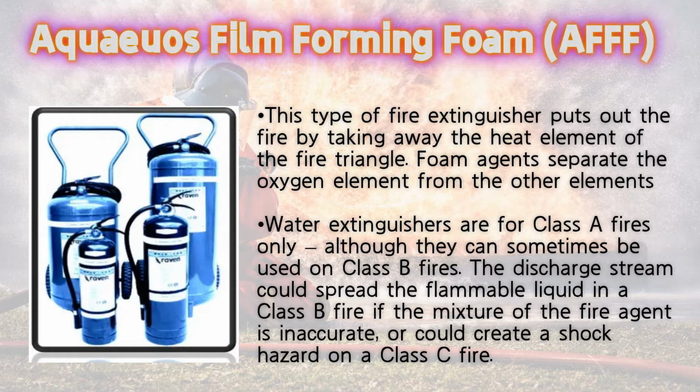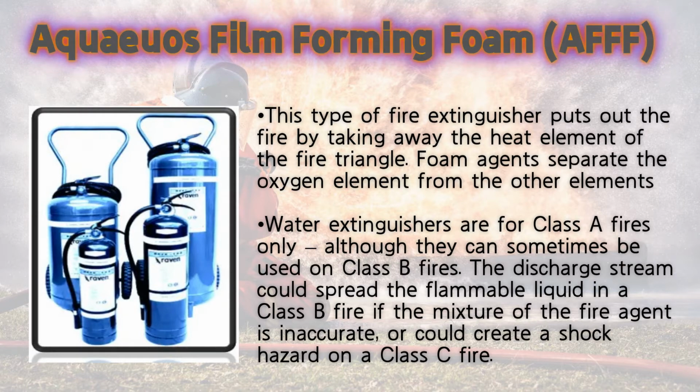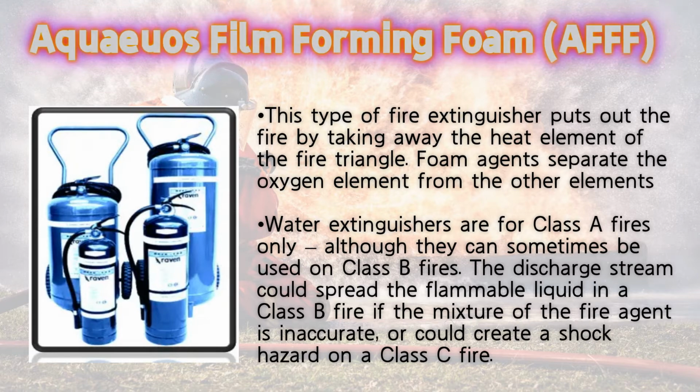Water extinguishers are for Class A fires only, although they can sometimes be used on Class B fires. The discharge stream could spread the flammable liquid in a Class B fire if the mixture of the fire agent is inaccurate, or could create a shock hazard on a Class C fire.